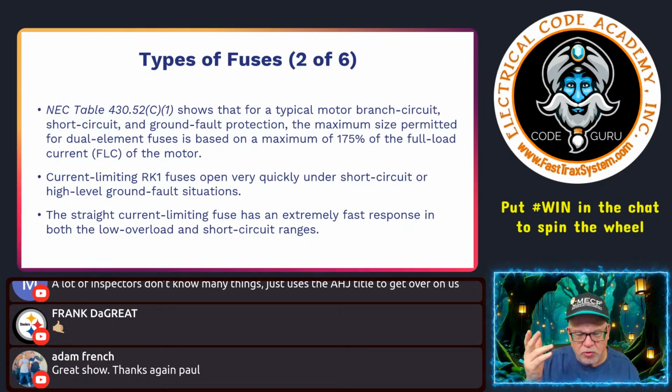You'll have some allowances for different types of fuses, like CC fuses. But in general, this is a maximum. You don't exceed it. Can you be less than it? Yes. Can you be more than it? Not unless the note says otherwise. And these aren't informational notes. These are notes that are very much applicable where referenced. For example, inverse time breaker references a note 2. Note 2 says if it's a non-adjustable, those types of things, we'll let you do this, that type of thing.